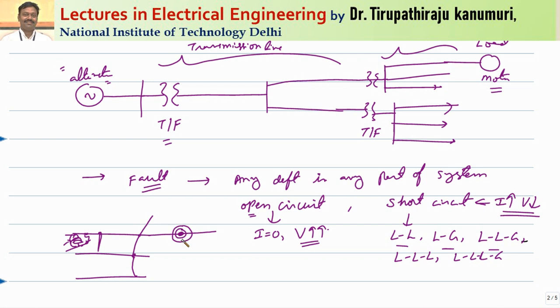Coming to alternators, transformers, or motors — their windings and conductors are protected by insulation. Over time, the insulation absorbs moisture, which causes it to lose its dielectric strength. Because of this, leakage current may start passing and sometimes breakdown may happen between two conductors. In transformers or alternators, these faults are called inter-turn faults or inter-phase faults, depending on whether they occur between two adjacent turns or two adjacent phases.